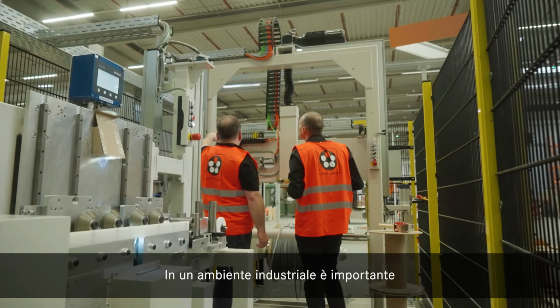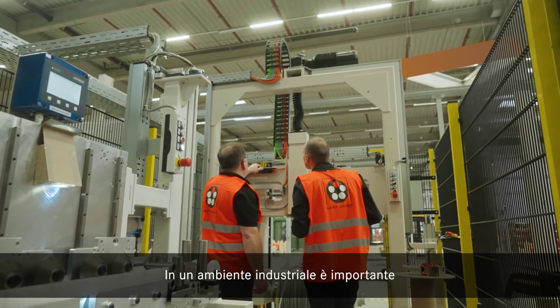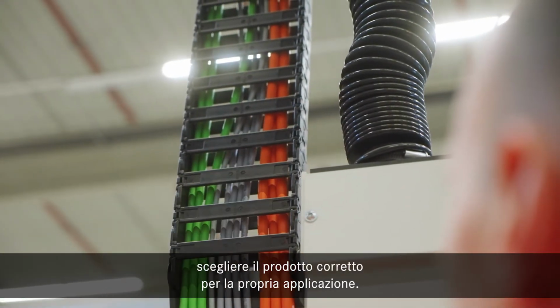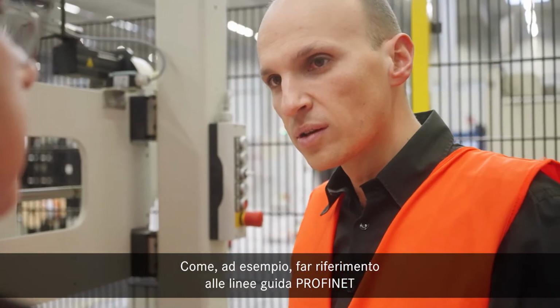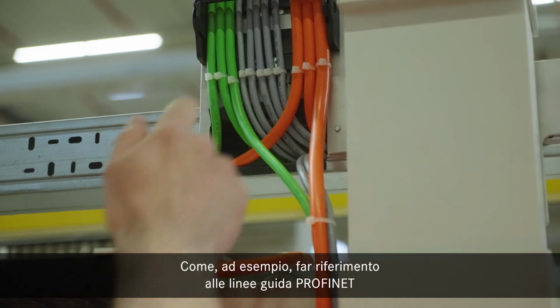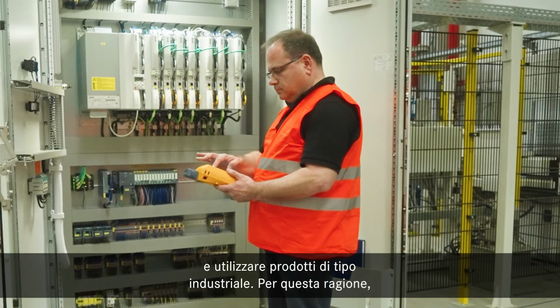Most root causes for problems can only be detected visually. In industrial environments, it is important to choose the right products for the application. For example, to follow the Profinet guideline and use industrial-grade products. So we check all connectors and cables and especially the harnessing.